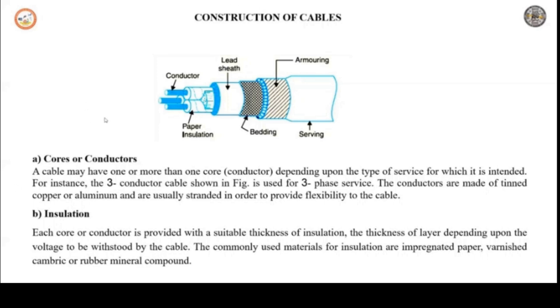Next is the metallic sheath. The insulated conductors are covered by a lead sheath or aluminum sheath. This provides mechanical protection but mainly restricts moisture and other gases from reaching the insulation.